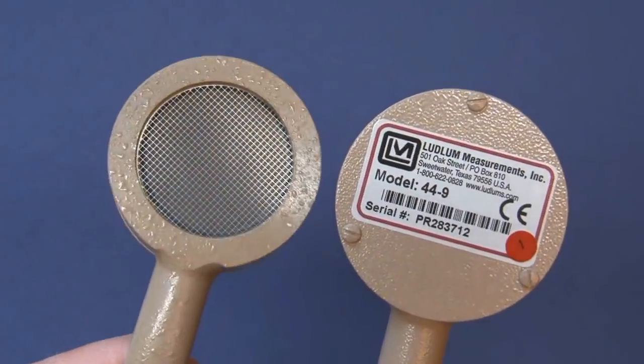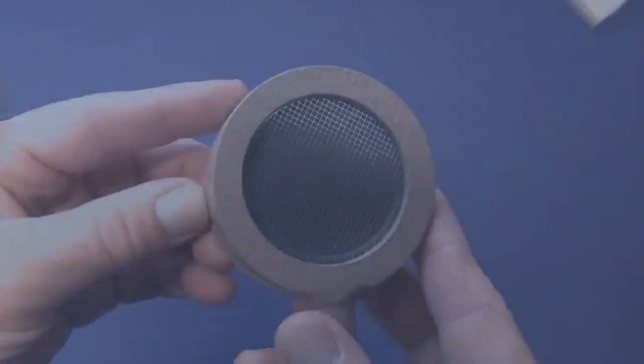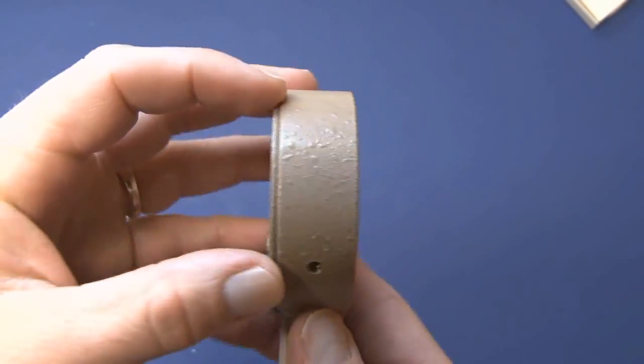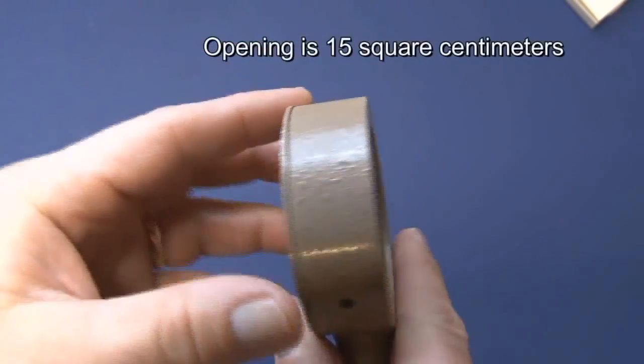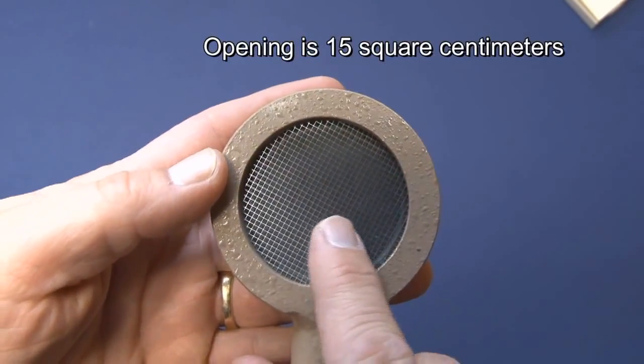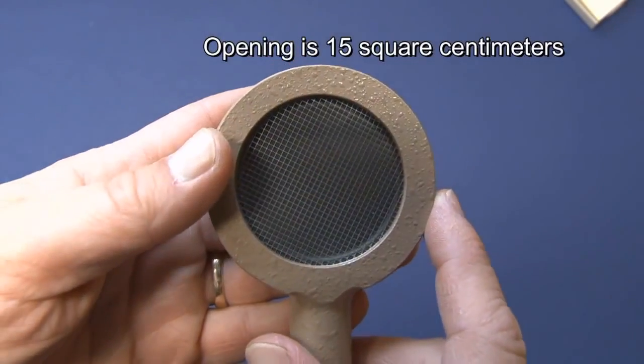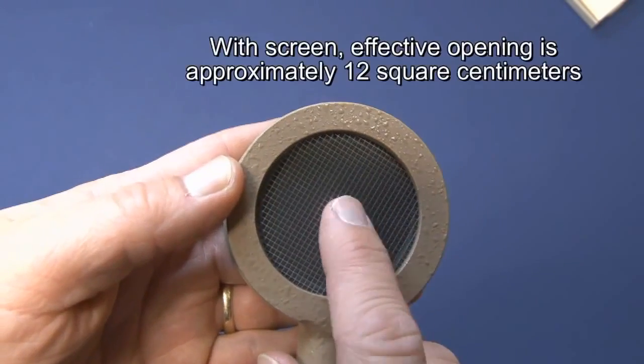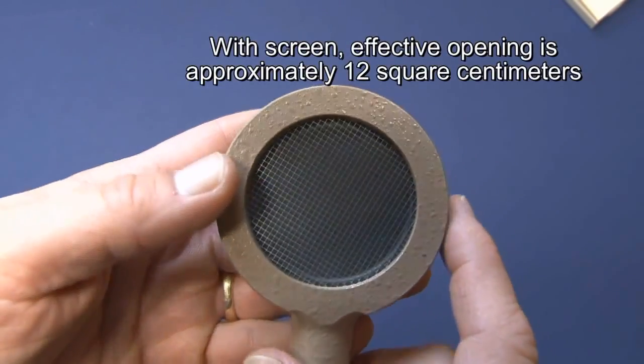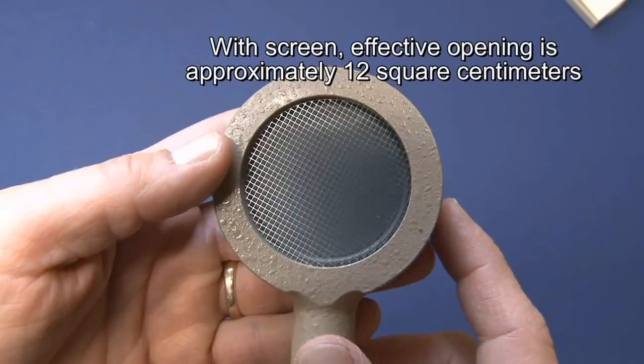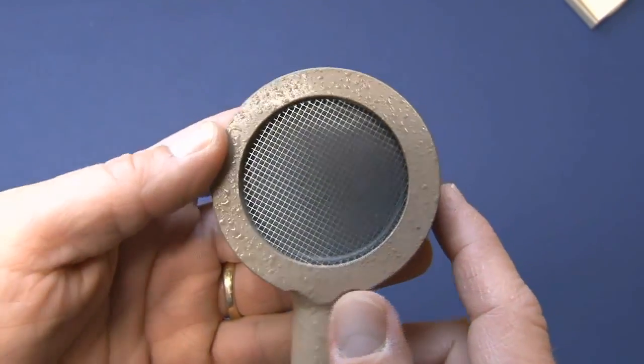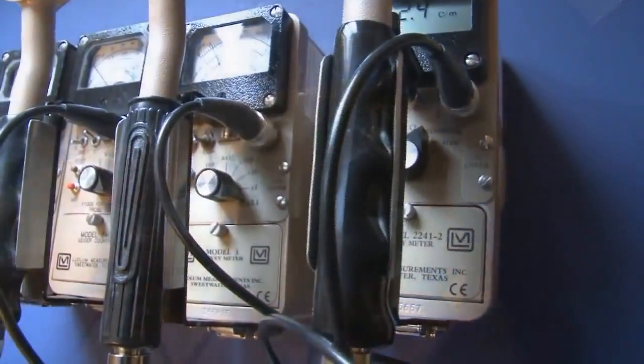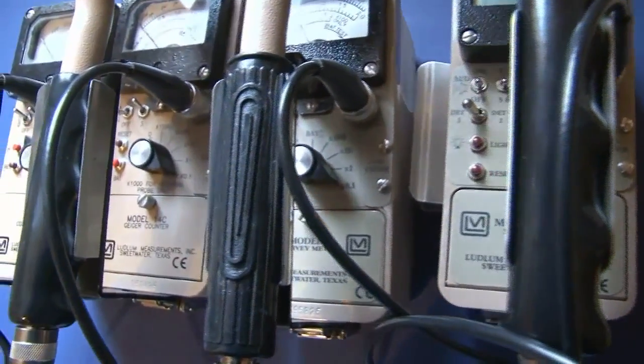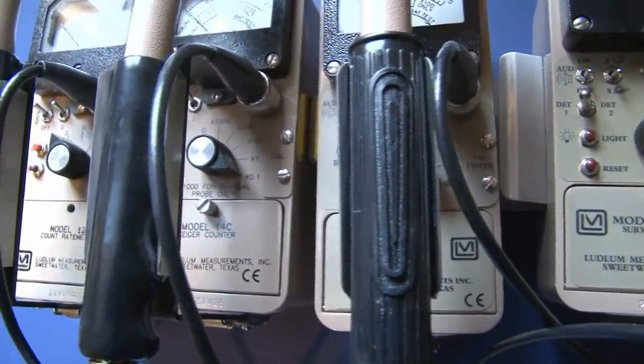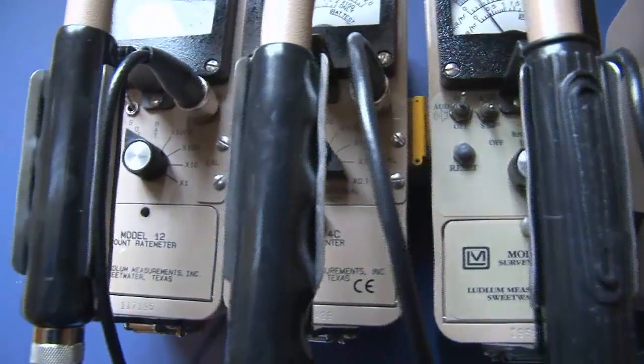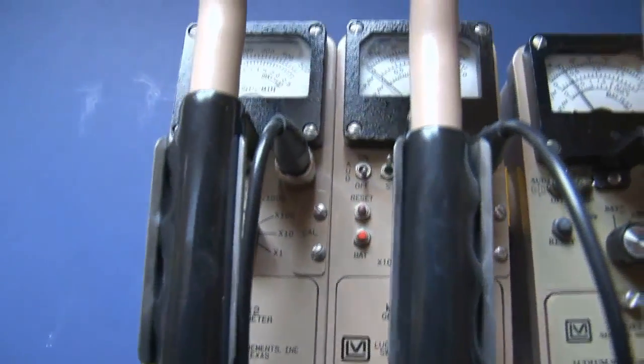If we look at the detector part of this, it's got an active window area of about 15 square centimeters, and you can see the little screen here that covers it. And if you take into account the open area of this screen, it gives you about 12 square centimeters of open area. The detector can be connected to a pretty wide variety of different survey instruments, any of them that operate between 850 to about 1,000 volts will work, 900 volts being ideal for this type of probe or this type of detector.